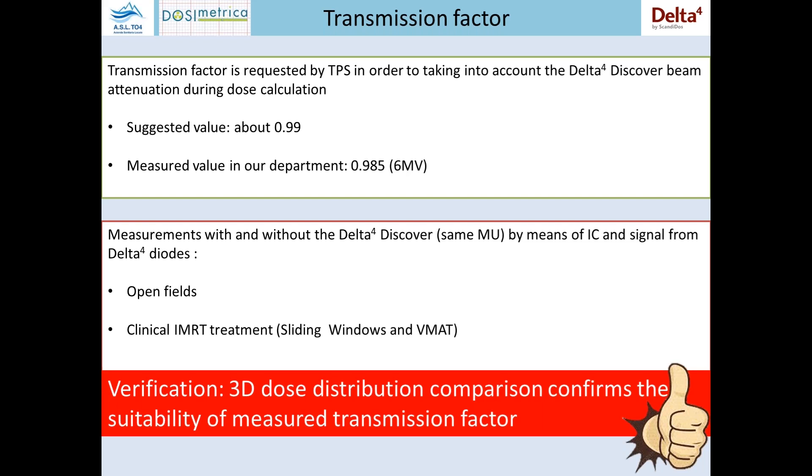It was necessary to insert the transmission factor in the TPS and in the record and verify system. In order to do that, we performed different measurements to verify the suggested values of 0.99. We made open field IMRT treatment measurements and found a mean value of about 0.985, very similar to the one suggested. We made these measurements with 6 MV only, because we use it especially with VMAT and similar techniques.